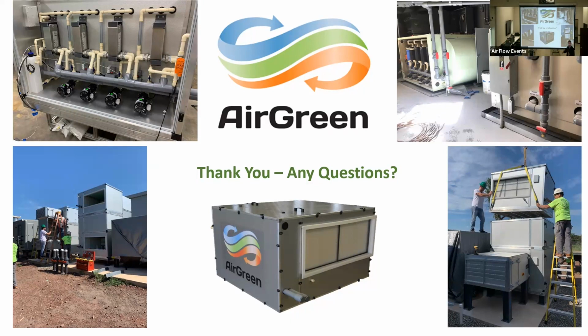it's better to buy 2 units at a lower price than a higher cost bigger unit. Then if something needs to be fixed, you still have something running. It's like if I have a fan wall and I've got 4 fans and 1 fan breaks, I still got 3, right? We've seen, certainly on the refrigeration side, that the cost of a unit twice our size was 3 times as much. So it's cheaper to have 2, have some redundancy, than to spend more money on a bigger unit. But we're working our way towards a solution for 15,000 CFM.